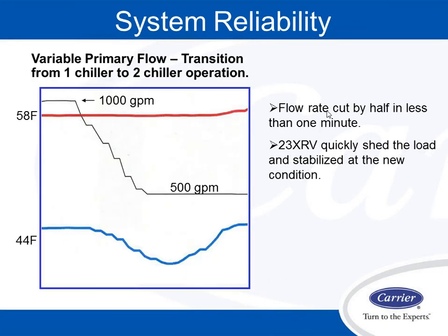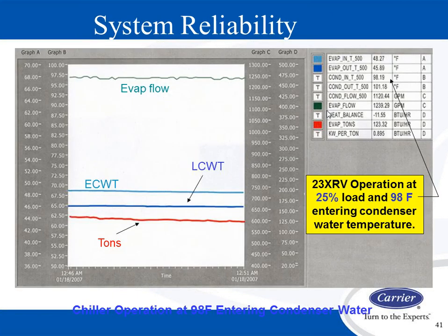operation. Here I show how it can respond. Again, here we cut the flow in half in less than a minute, and the machine quickly stabilizes and operates. Look at operating with 25% load with extremely high condenser water temperature. So I've got 25% load, 98-degree entering condenser water. Try that with a centrifugal. It will not operate very well. In most cases, it will probably surge.